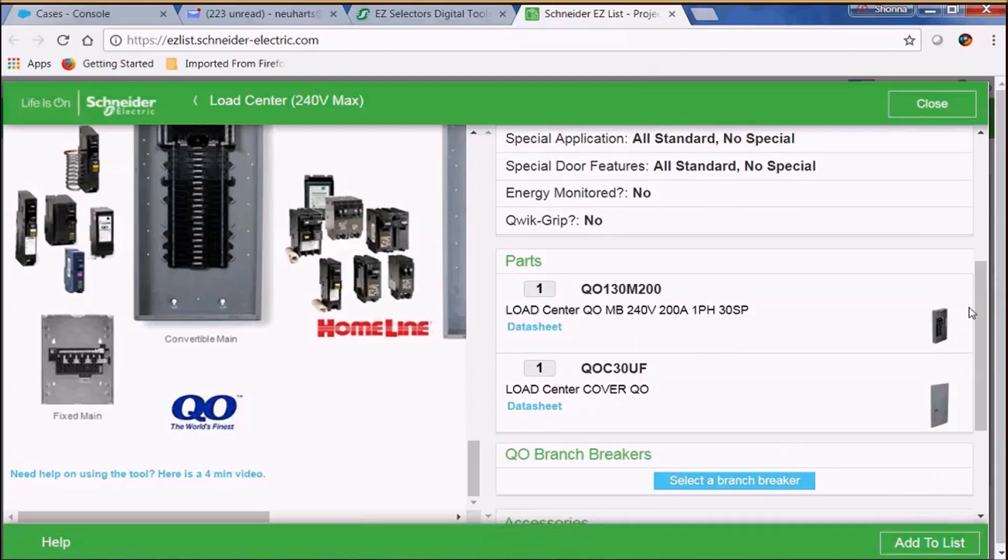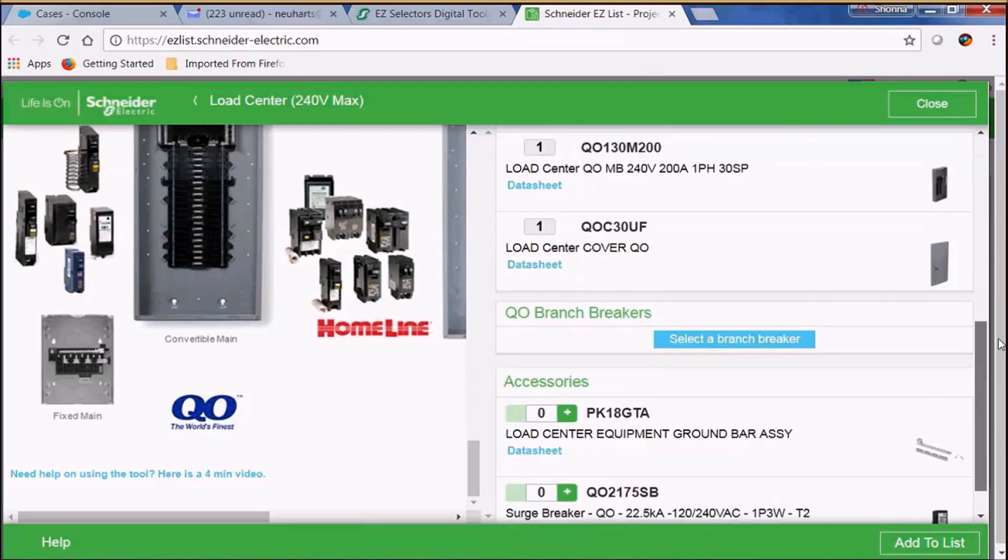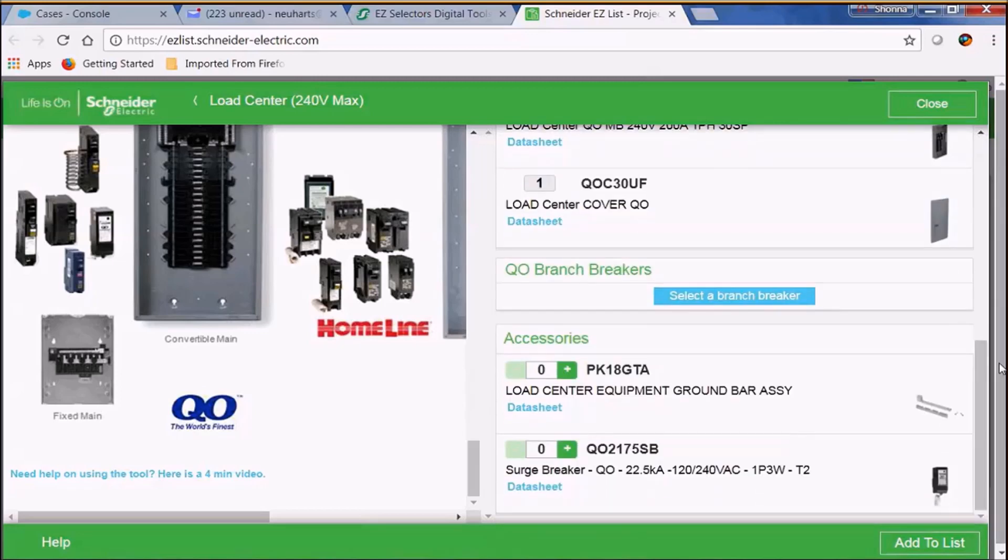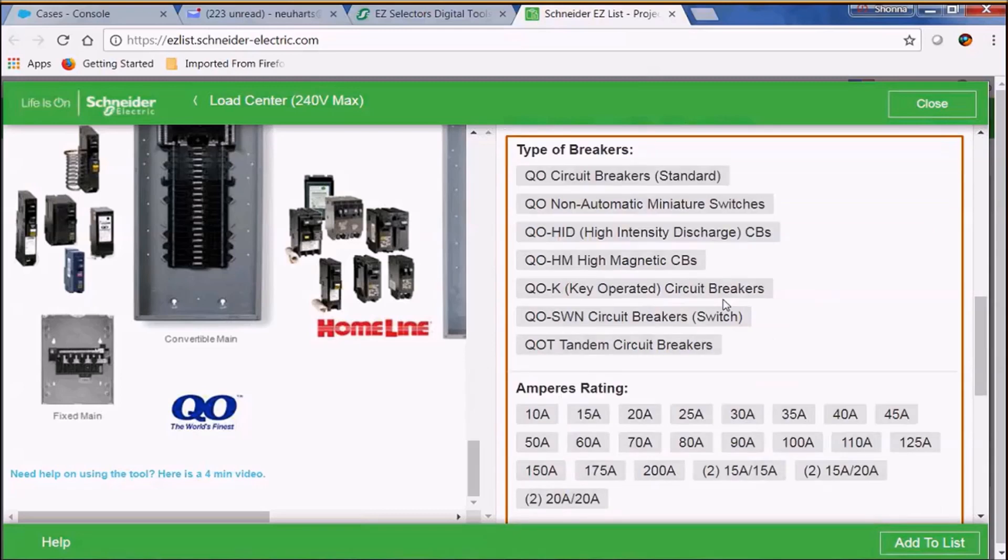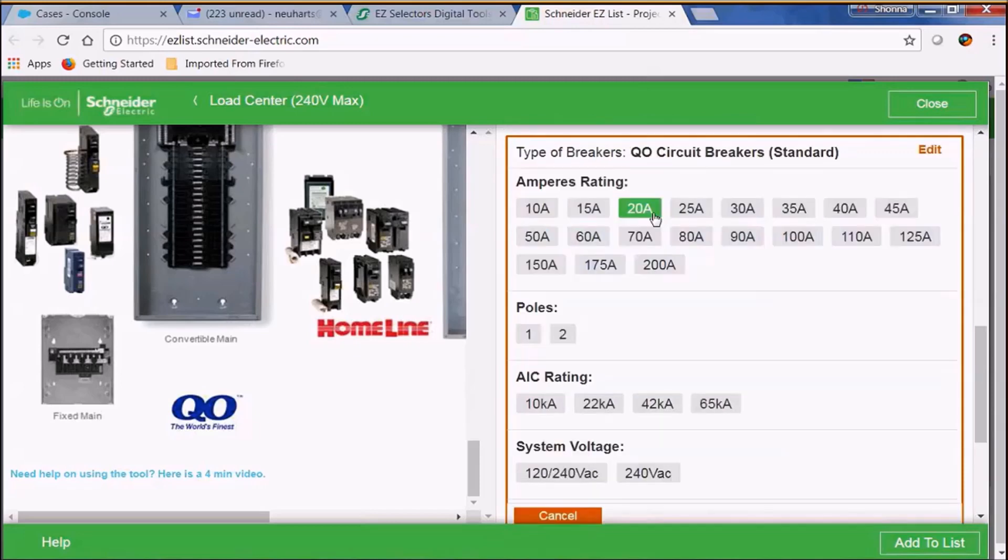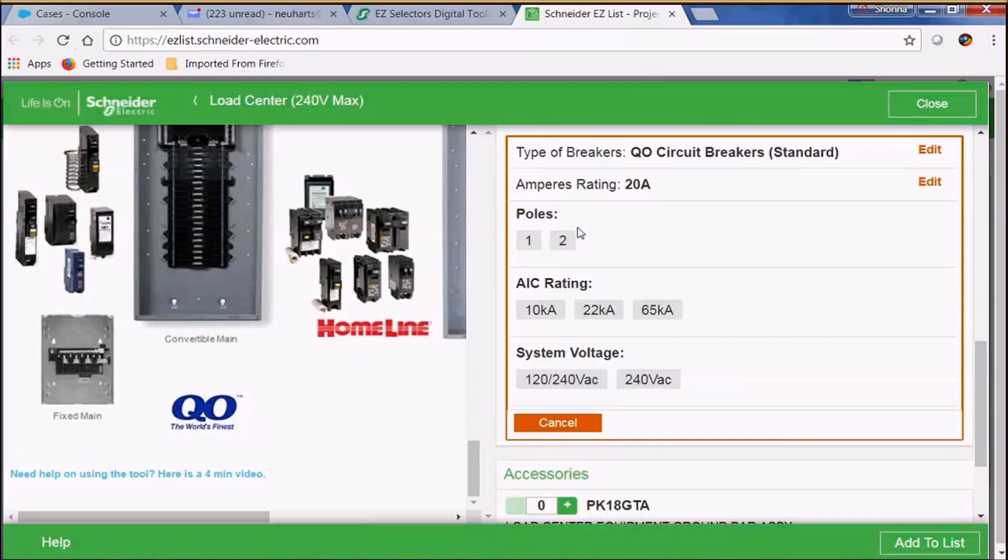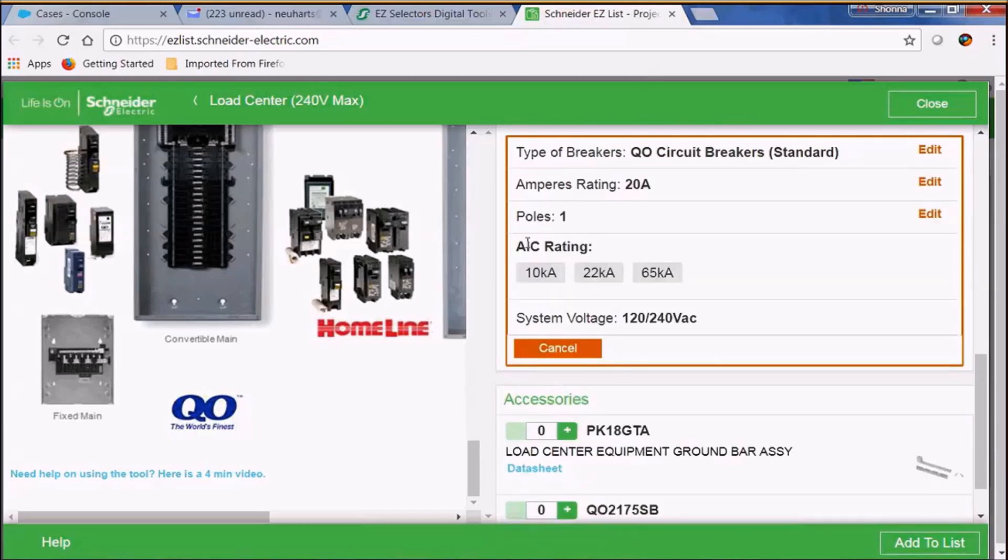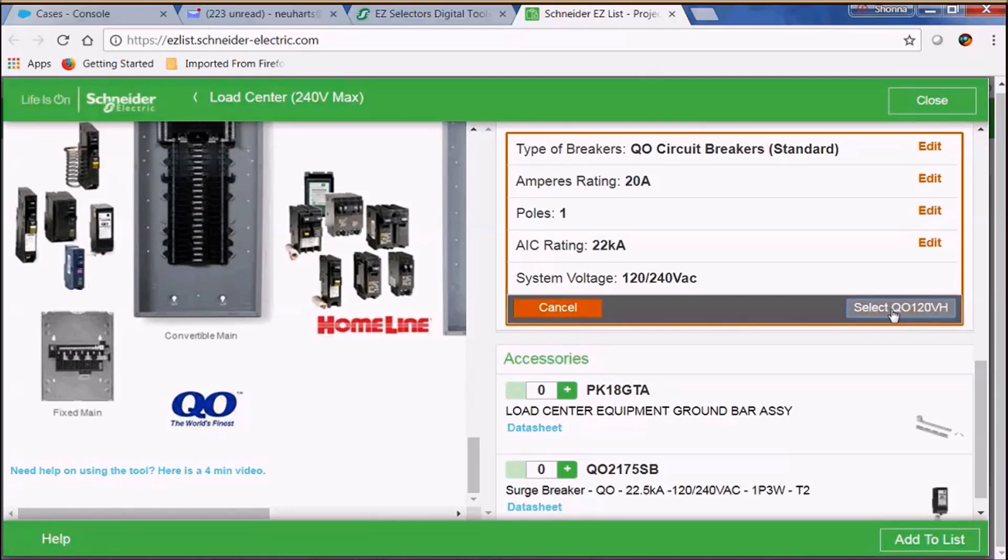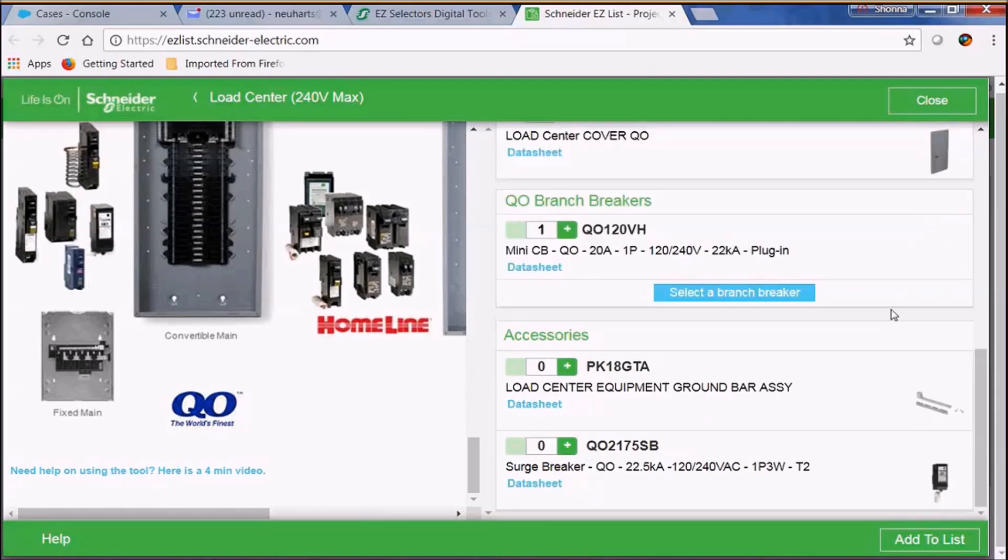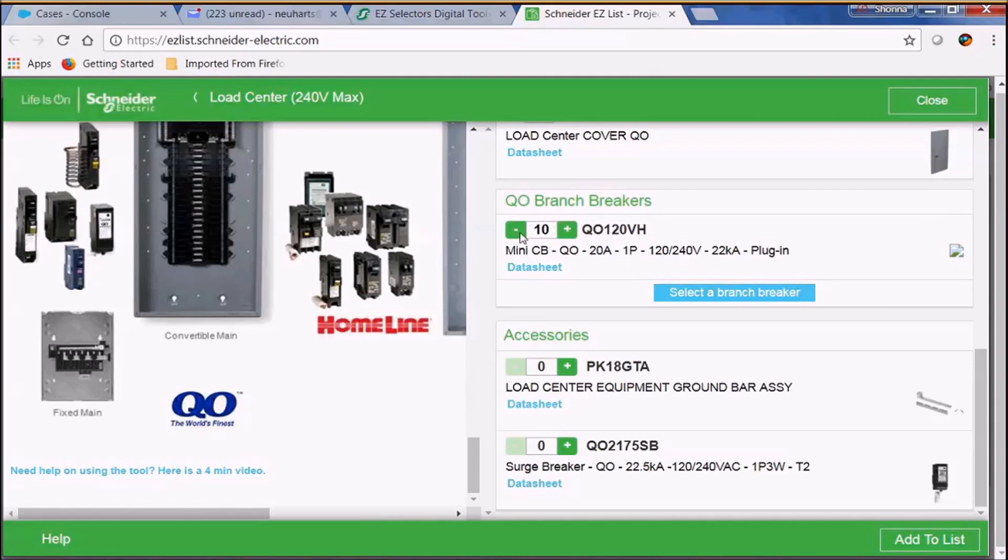We have an opportunity now to start making our breaker selections so why don't we go ahead and do that. The type of breaker that we're going to start with is our standard QO circuit breaker. We're going to select 20 amp one pole and 22k AIC. As you'll notice here you have an opportunity to select the QO120VH. Now you can go and scroll up and down to select the quantity of breakers that you'd like to have.